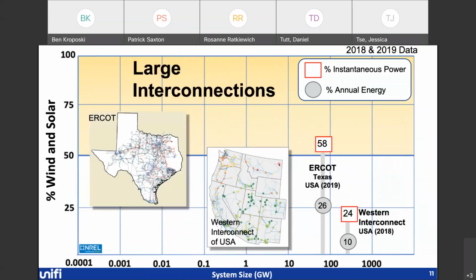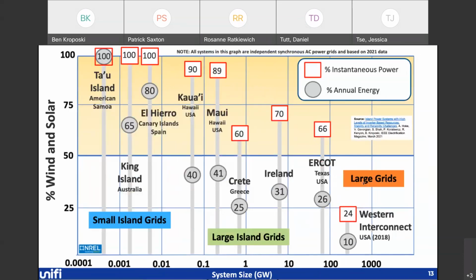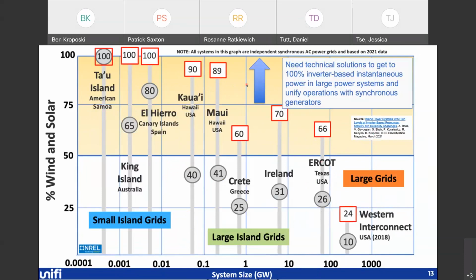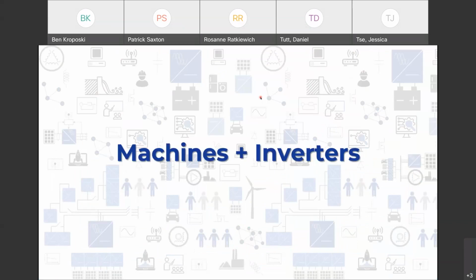And then as we look at larger interconnections, two examples here, ERCOT, the Texas Power Grid, and the Western Interconnect of the United States. Actually, ERCOT earlier this year was able to run at 66% instantaneous wind and solar. So these are creeping up, but at the end of the day, you can see here everything together. What we need to do is find solutions to the technical challenges to get these levels much higher. So we really need to look at how the power systems operate at all times during the entire year and make sure that we come up with solutions for getting to 100% inverter-based instantaneous levels. And then you can imagine during the year it's going to fluctuate with the amount of synchronous generators that you have online. So a little bit of the technical challenges with integrating machines and inverter technologies.